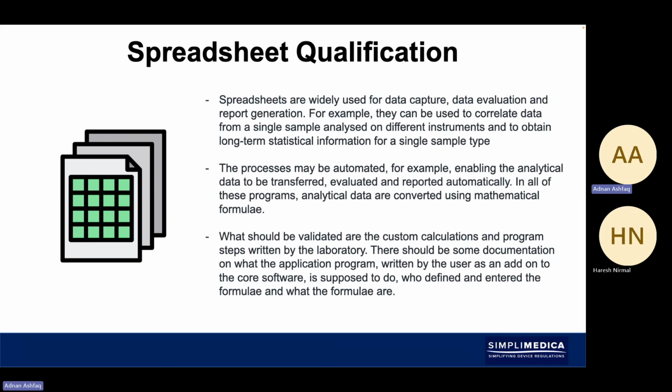that even in the design and development stages of a medical device, you may use an R&D Excel spreadsheet to make calculations which could have an integral impact on the safety of the device, through the calculations that you're using in the formula, even at the R&D stage, because that's going to eventually be built into the design of the device.